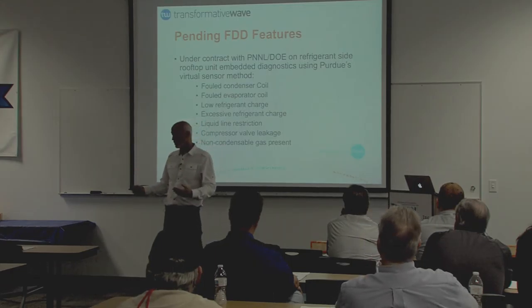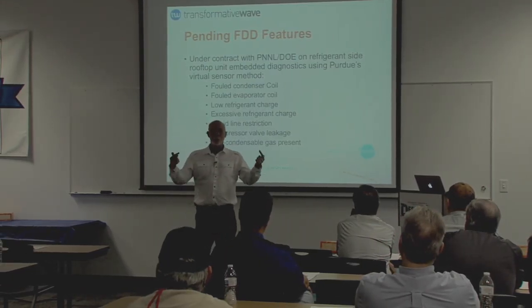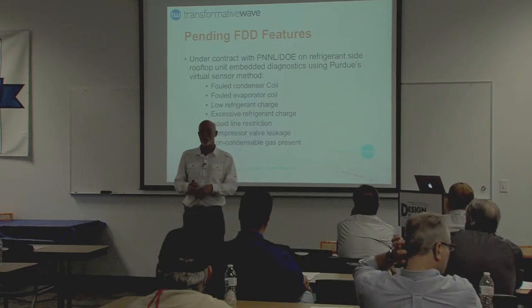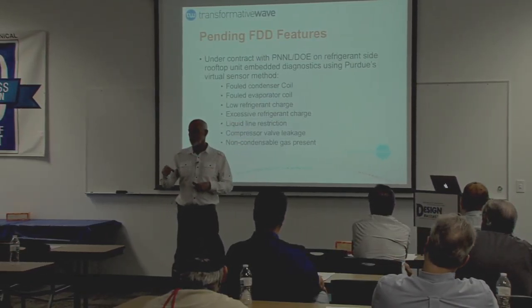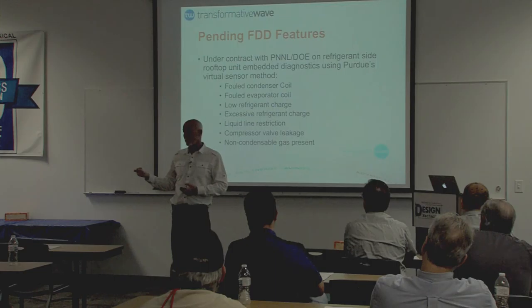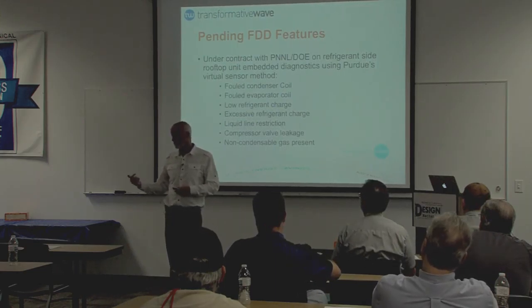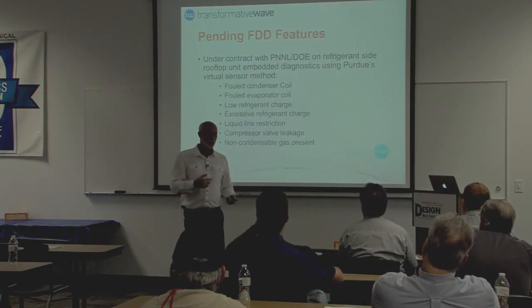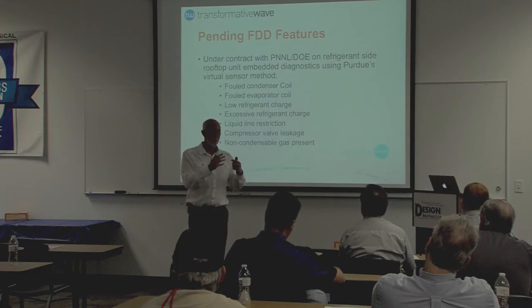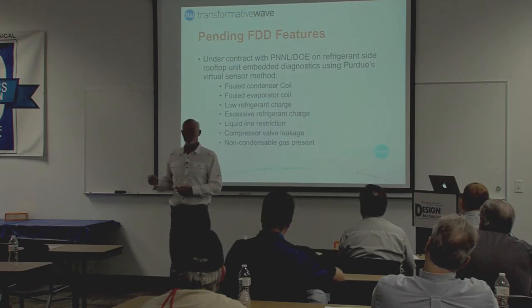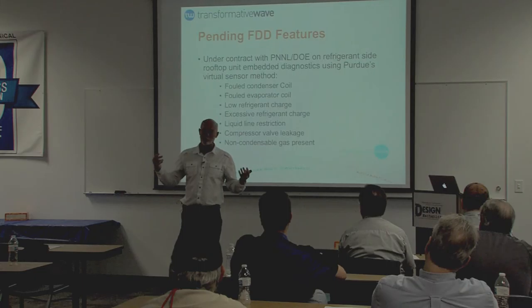Now, ordinarily in our industry, those of us who work with these machines understand how important it is to know the pressures in the system. But when you put a pressure sensor or transducer on an existing refrigeration system, you expose a potential for leakage, losing refrigerant, which means you're going to have a low charge, causing other problems. There's this whole litany of things that happen, not to mention the EPA looking over your shoulders.